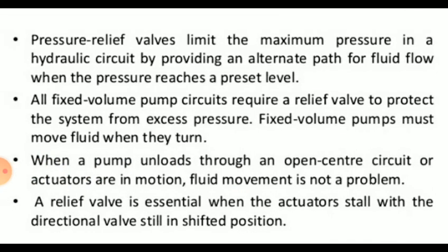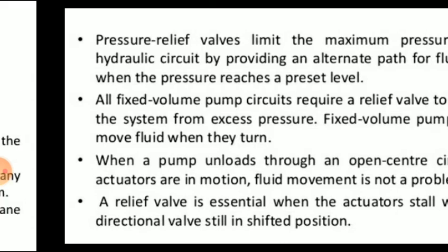So pressure relief valves limit the maximum pressure in a hydraulic circuit by providing an alternate path of fluid flow when the pressure reaches the preset level. All fixed volume pump circuits require a relief valve to protect the system from excess pressure. Fixed volume pumps must move fluid when they turn. When a pump unloads through an open center circuit or actuators are in motion, fluid movement is not a problem. A relief valve is essential when the actuators stall with the direction valve still in shifted position.